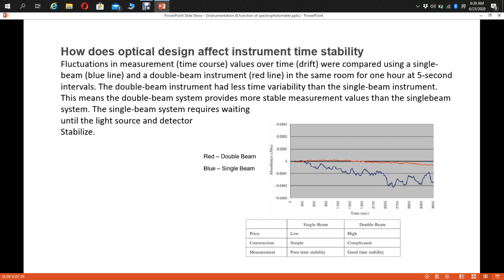The fluctuation in the measurement can be compared between the single beam and the double beam spectrophotometer. This line has less time variability than the single beam. The variation in absorption with the passage of time is very small compared to the single beam. This means the double beam system provides more stable measurement than the single beam system. The single beam system requires waiting until the light source and the detector stabilize, or you may say the instrument requires warm up time before the analysis, but not in the case of the double beam.